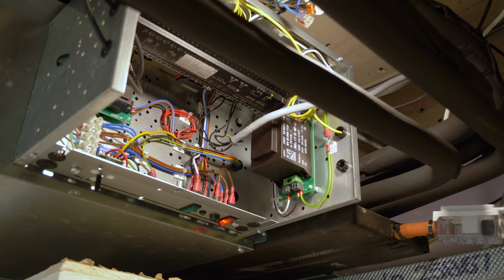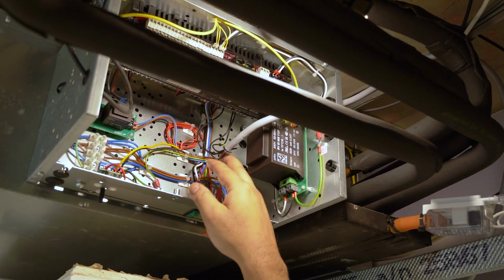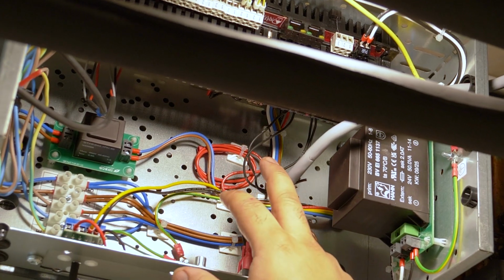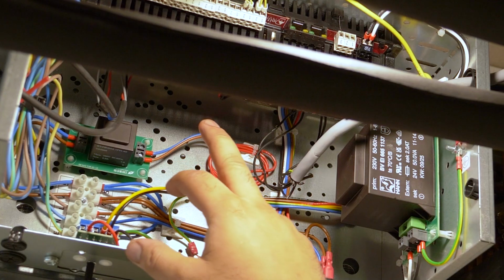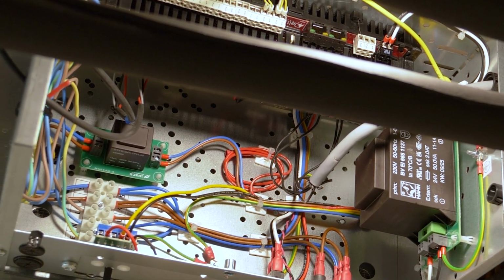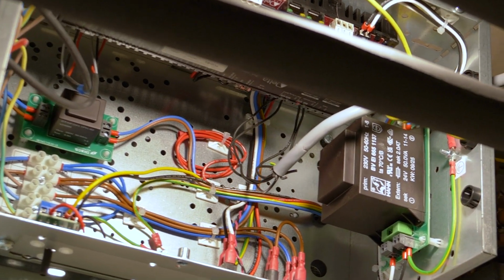So if you have a BMS, you want BACnet, you want TCP/IP, or you want Ethernet, we will configure the fan coil units and assign it with an IP on the controller. So then when it comes to site commissioning on a large project, it goes as smooth as possible.